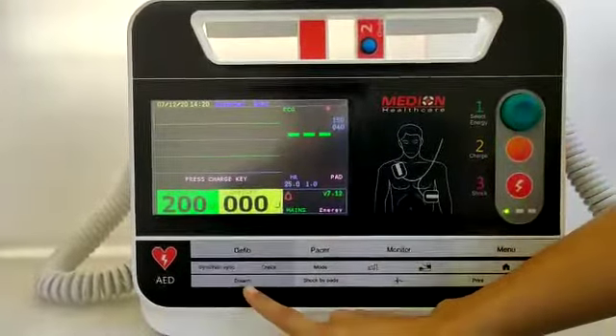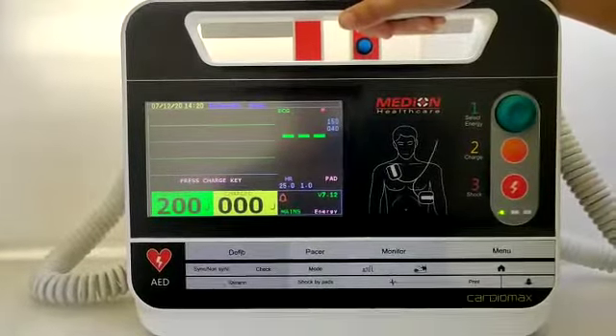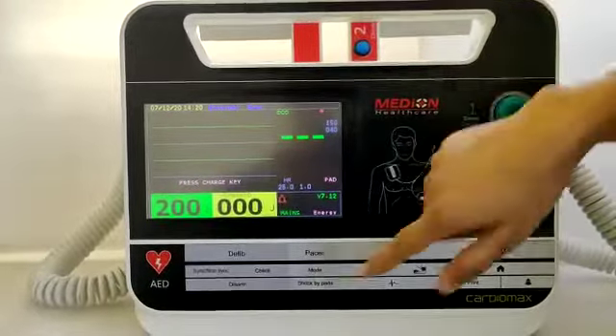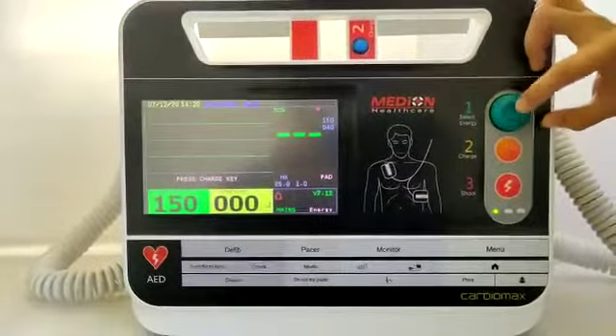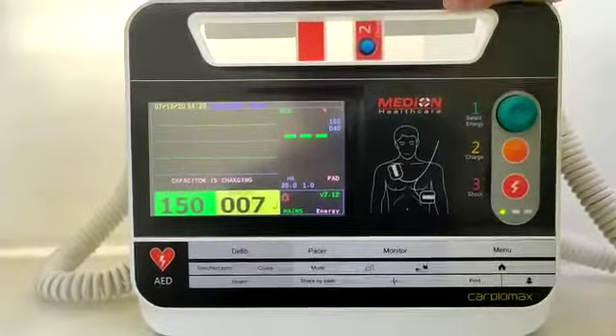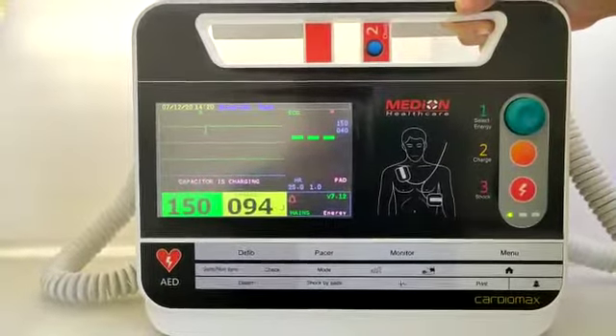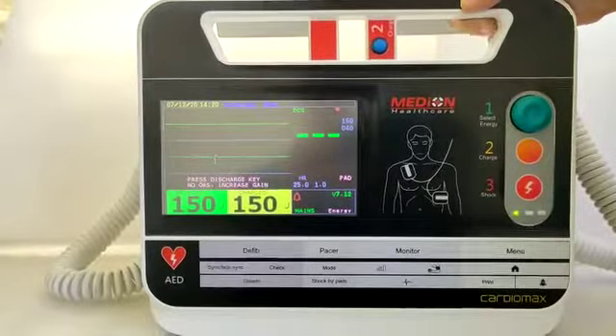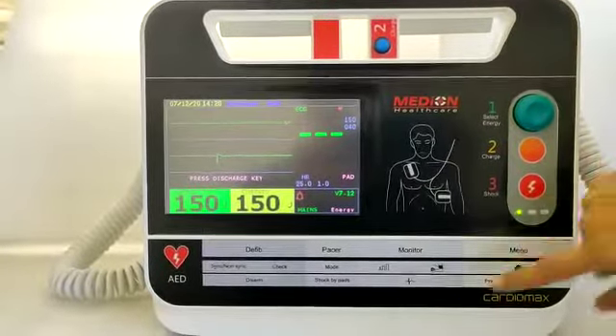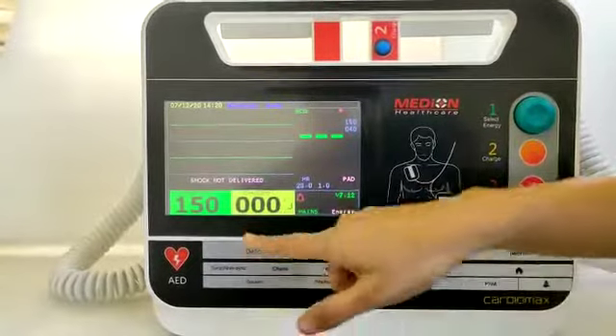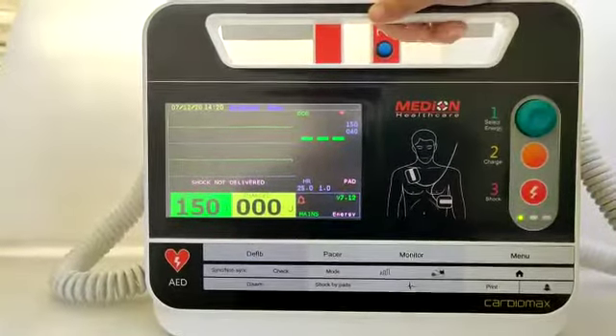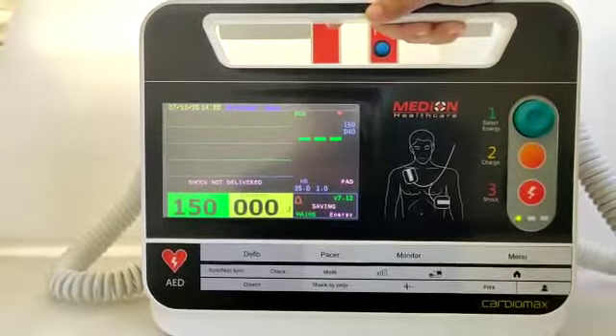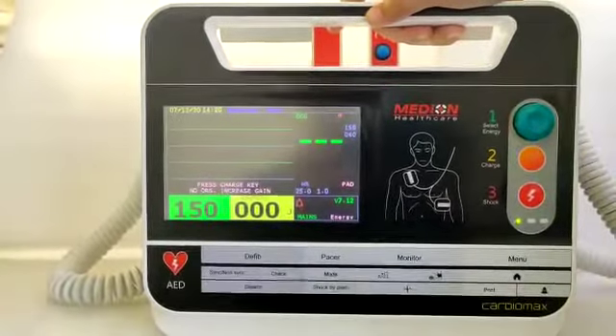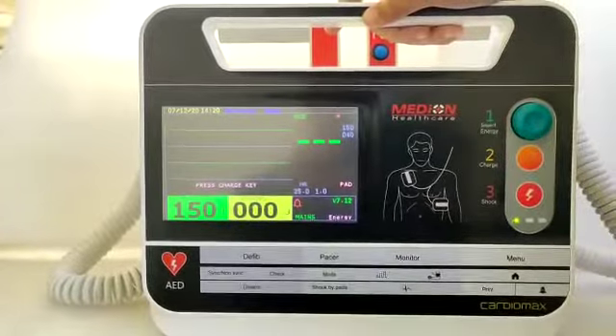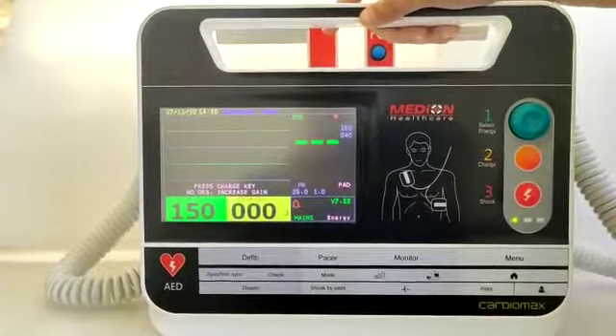This is a disarm feature. The disarm feature is used to disconnect the capacitor from the internal circuit. So we'll see the demo. Here I am selecting energy 150 and then charge. And if the user doesn't need to discharge the shock, he can disarm. So the capacitor will get discharged automatically. Also, there is an auto discharge feature in which, if the shock is not delivered within 20 seconds, the capacitor will get discharged automatically.